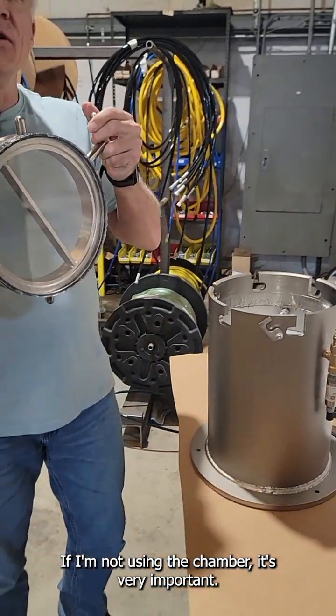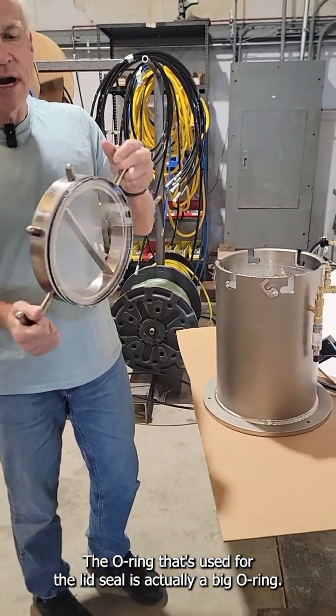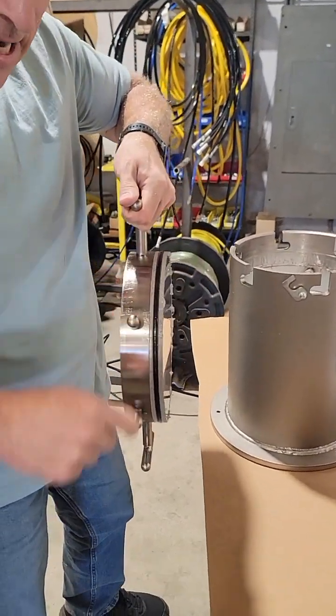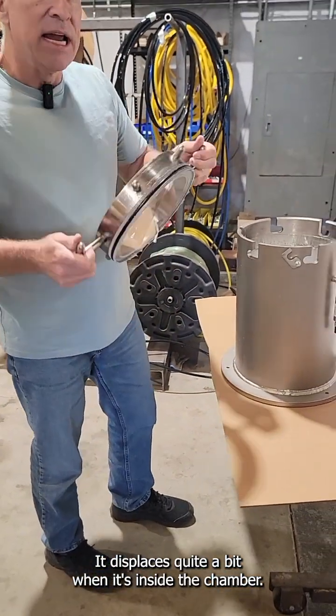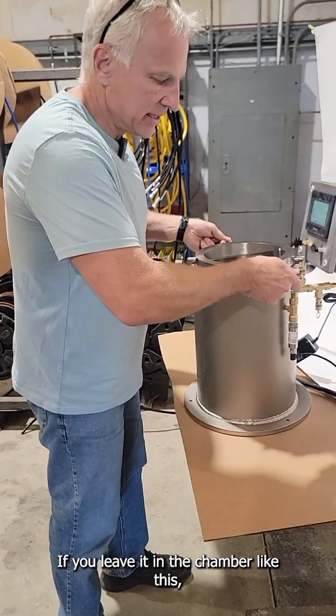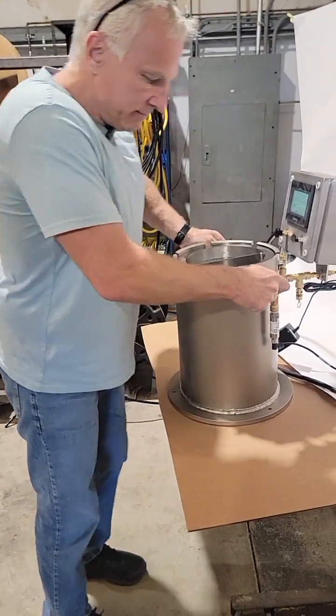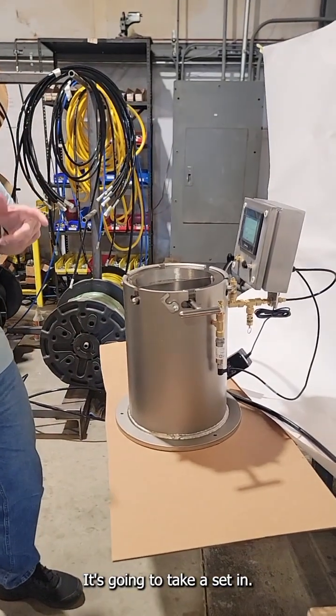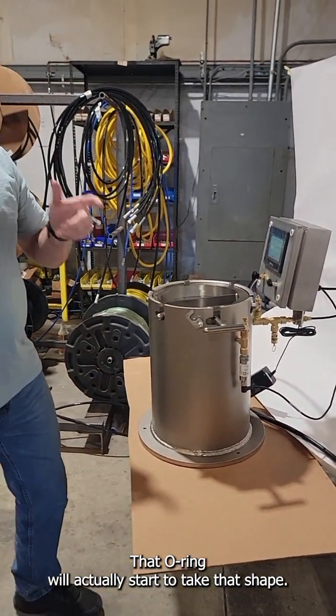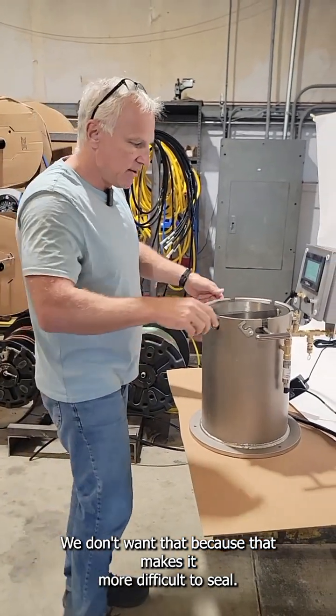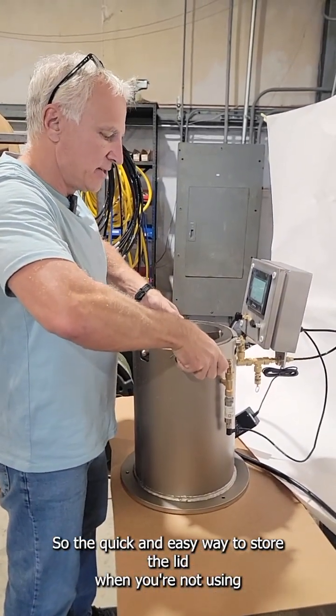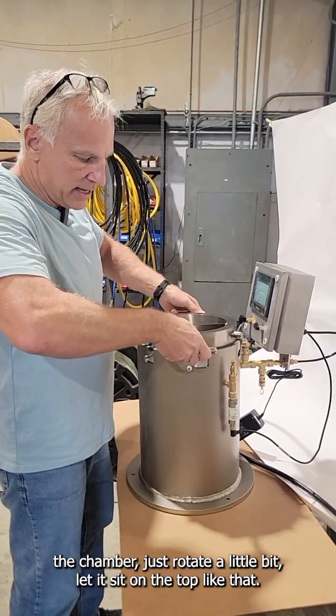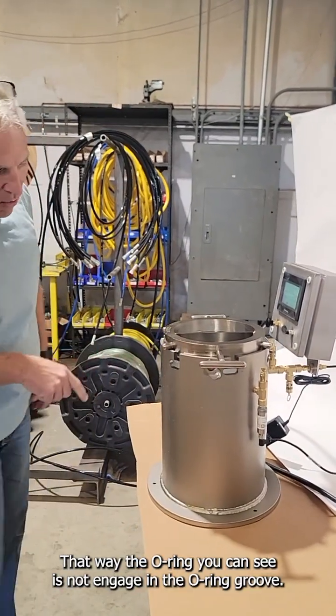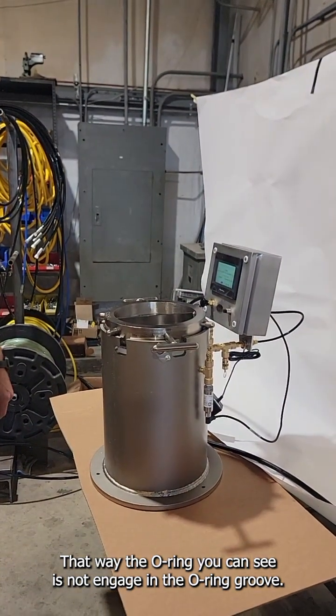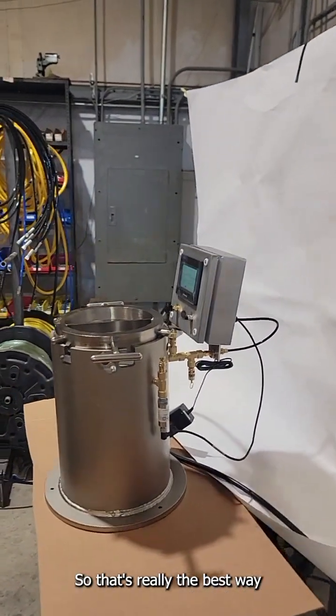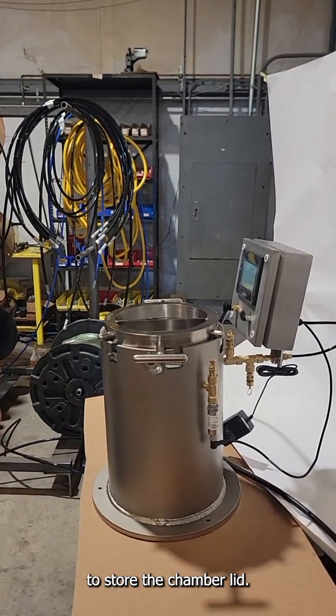If I'm not using the chamber, it's very important: the O-ring that's used for the lid seal is actually a big O-ring. It displaces quite a bit when it's inside the chamber. If you leave it in the chamber like this, all the way down where it's engaging the O-ring groove, it's going to take a set, and that O-ring will actually start to take that shape. We don't want that because that makes it more difficult to seal. So the quick and easy way to store the lid when you're not using the chamber is to rotate it a little bit and let it sit on the top like that. That way the O-ring, you can see, is not engaged in the O-ring groove, so it won't take a set. That's really the best way to store the chamber lid.